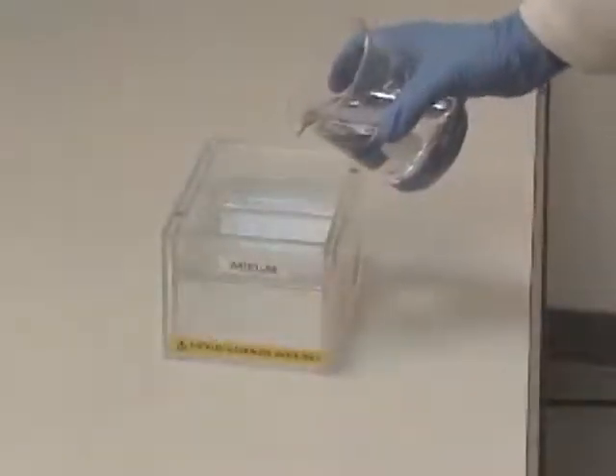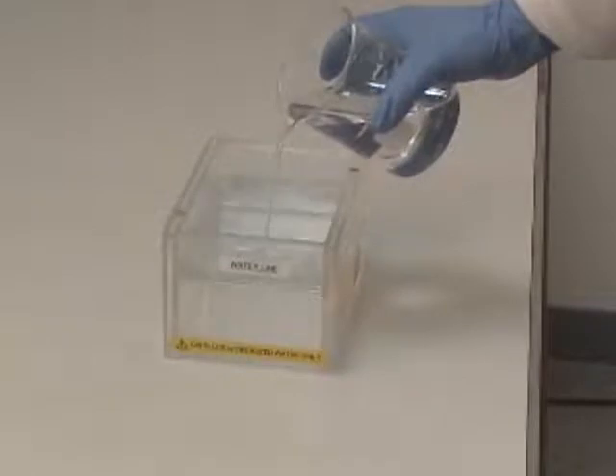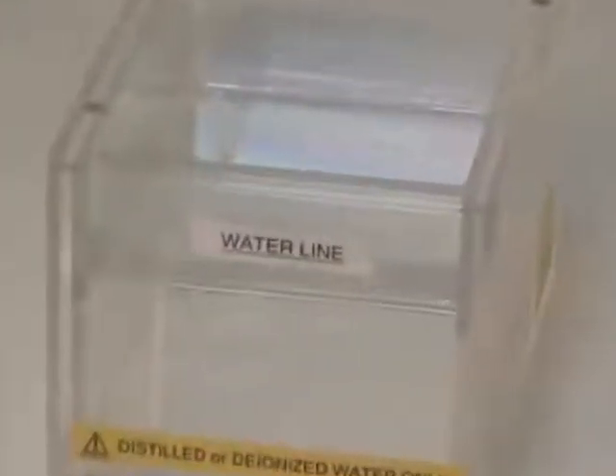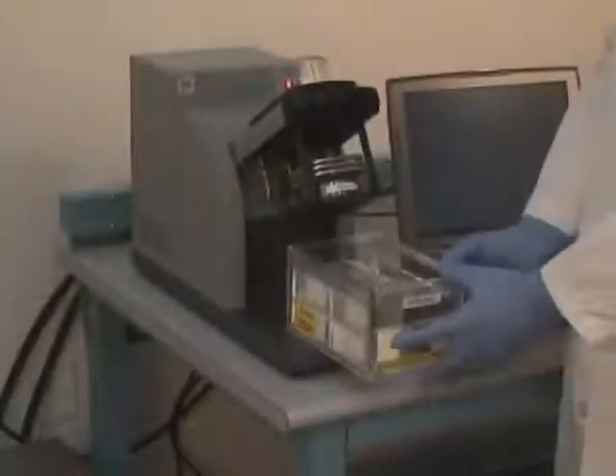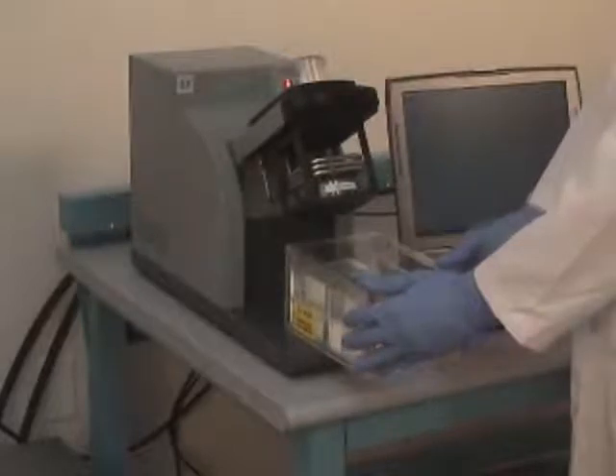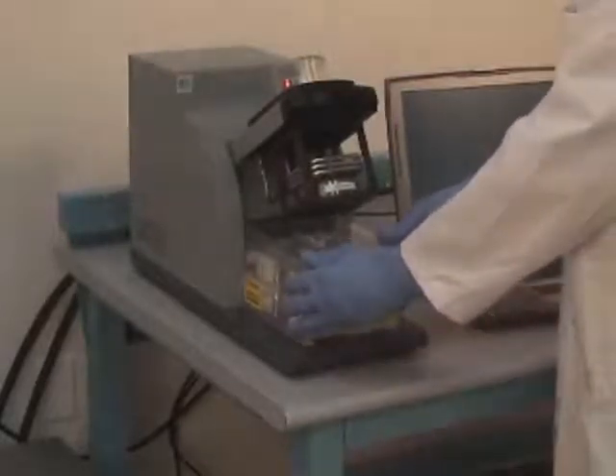To complete the installation, rinse the water tank with distilled or deionized water. This is the only type of water that should be used with the system. Fill the tank to the water line marked on the front, and position the tank under the acoustic assembly. Lower slowly to avoid splashing.